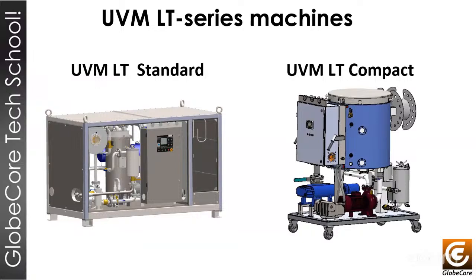Since the machine features no input pump installed, as mentioned above, the oil flow into the machine is facilitated by the vacuum pump. The diameter of the pipes has been increased, like in the other machines we mentioned. We increase the pipes, the filter, and the fillers of oil into the machine because we need to reduce the load on the vacuum pump and make it easy for the oil to get inside the machine using the vacuum in the system. The process equipment used in the machine, such as the heater, is completely equivalent to the standard dual pump units. The vacuum chamber features an increased volume for improved efficiency in thermal vacuum drying.